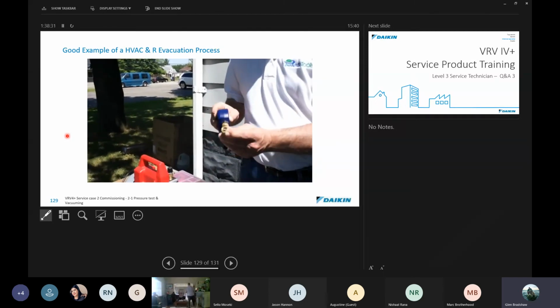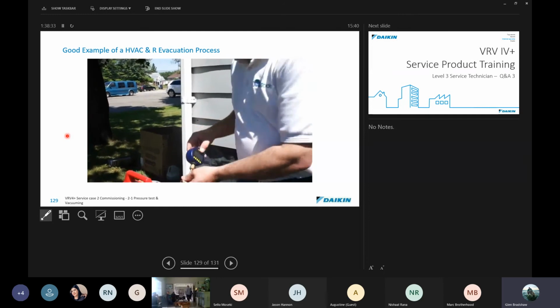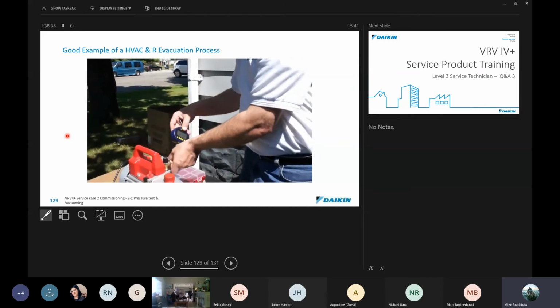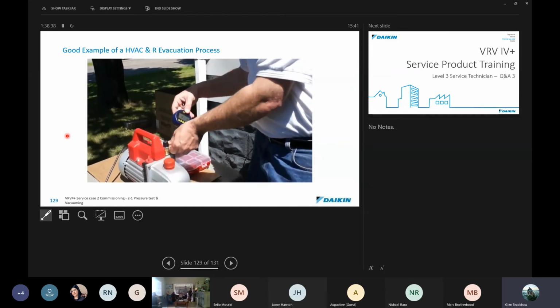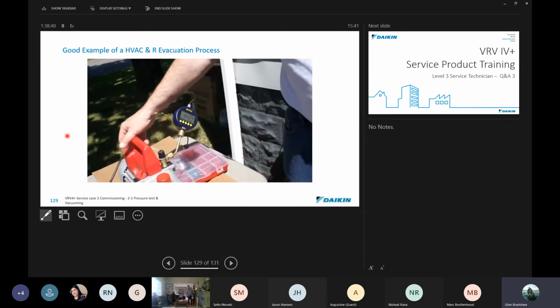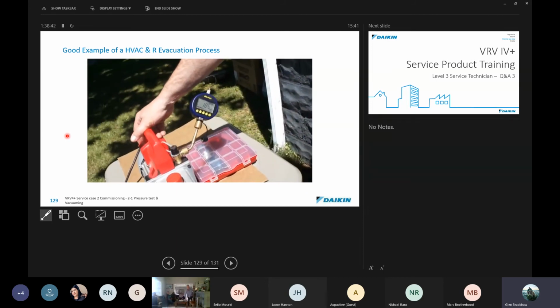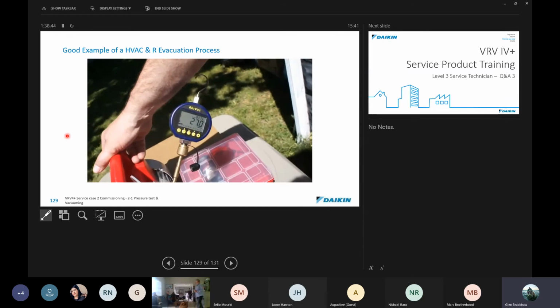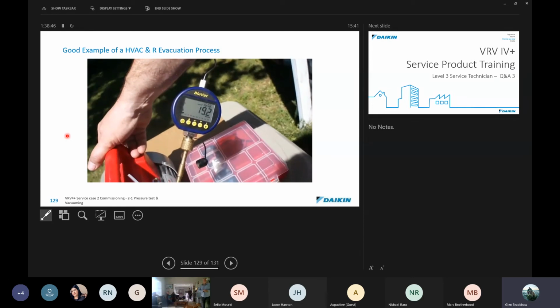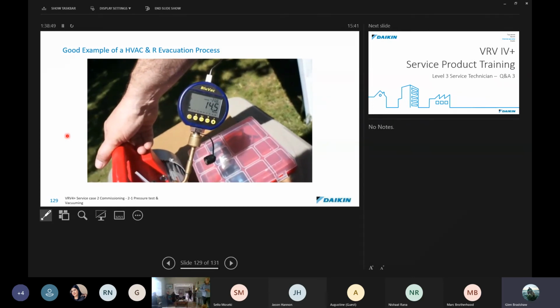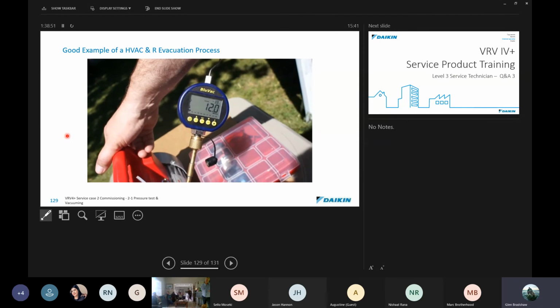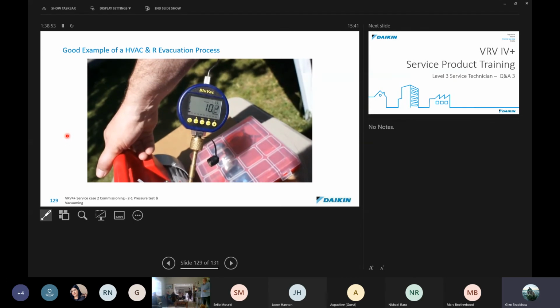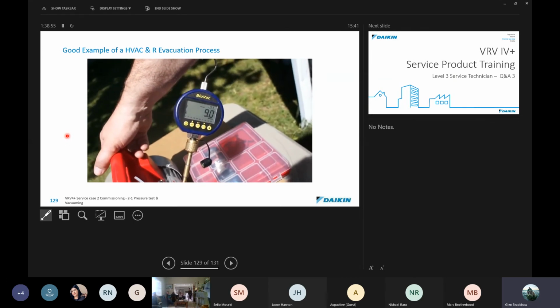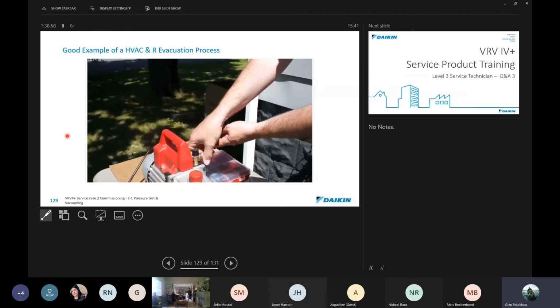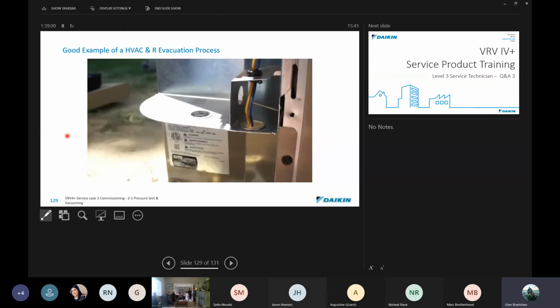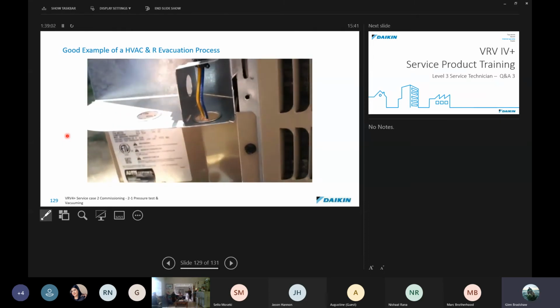All right, so we've got a small amount of Nylog already put on all the fittings. We're going to test this pump out and see how far down it will pull on its own. All right, so the pump's already down to below 17 microns, 15 microns, 14. So the pump is very adequate for doing what we want to do. So let's go to the next step. Pulls down 9 microns.